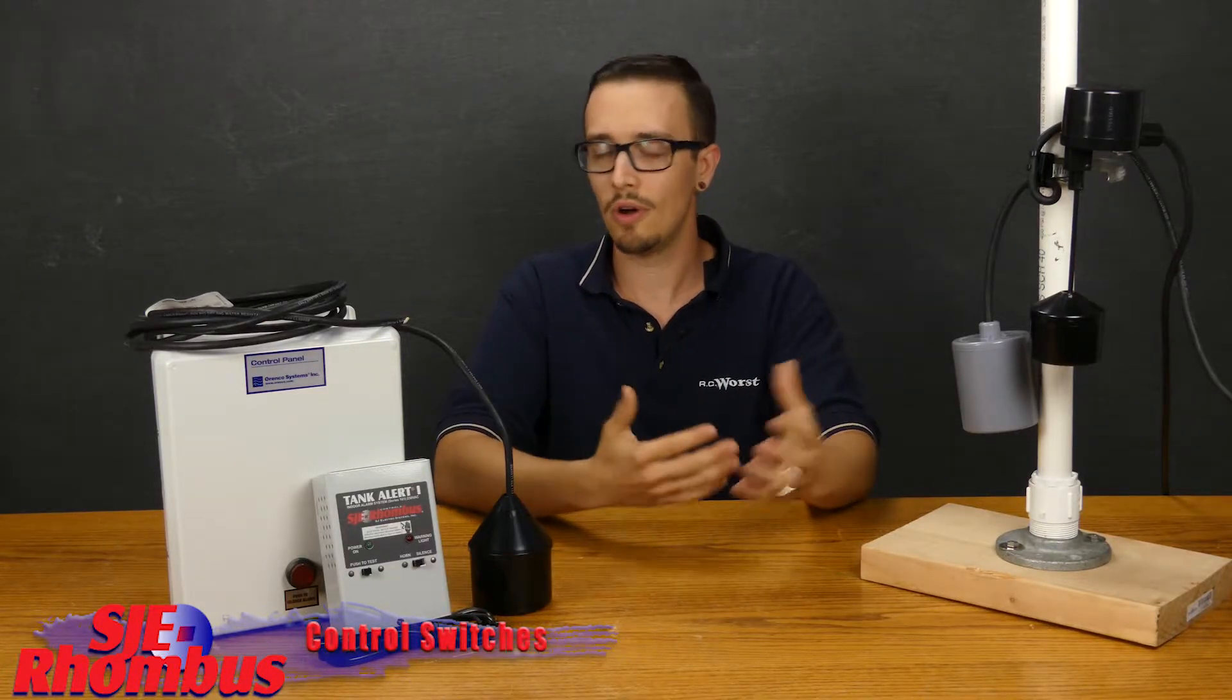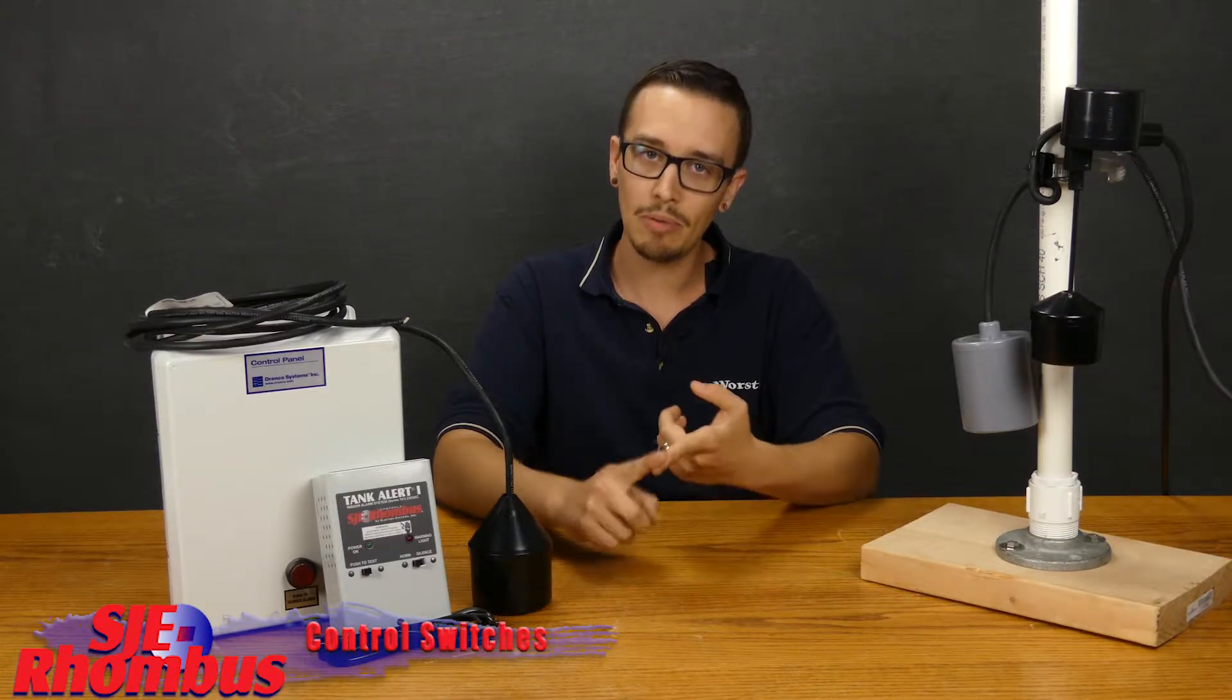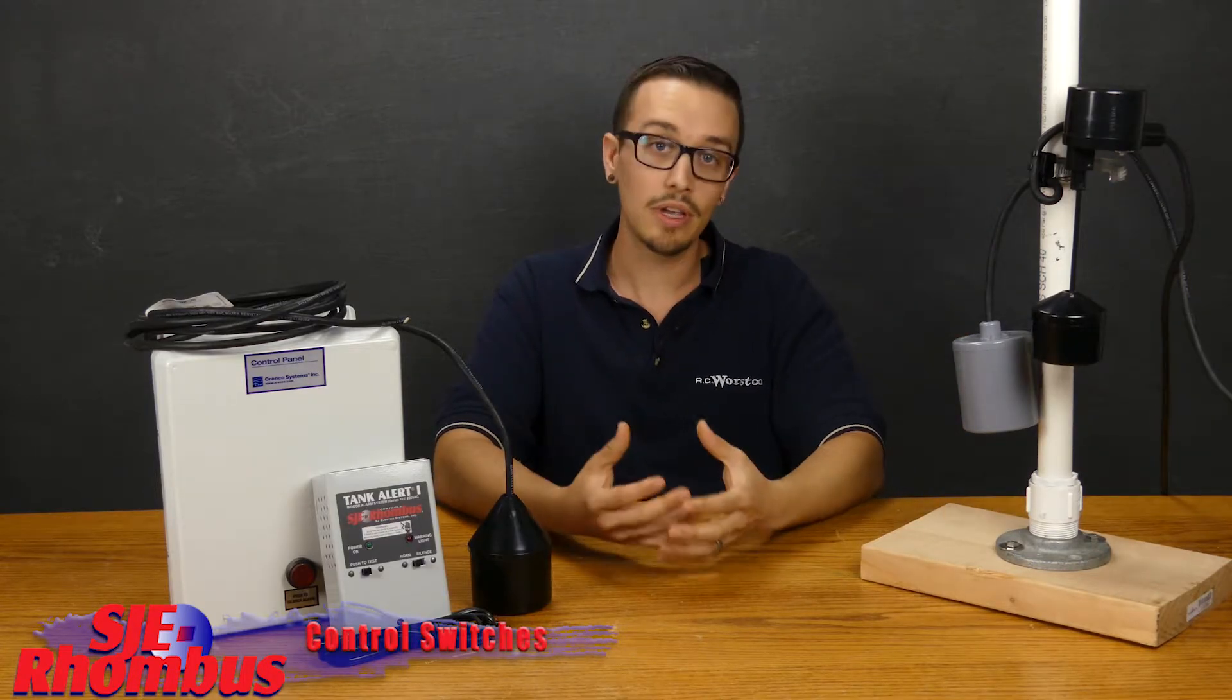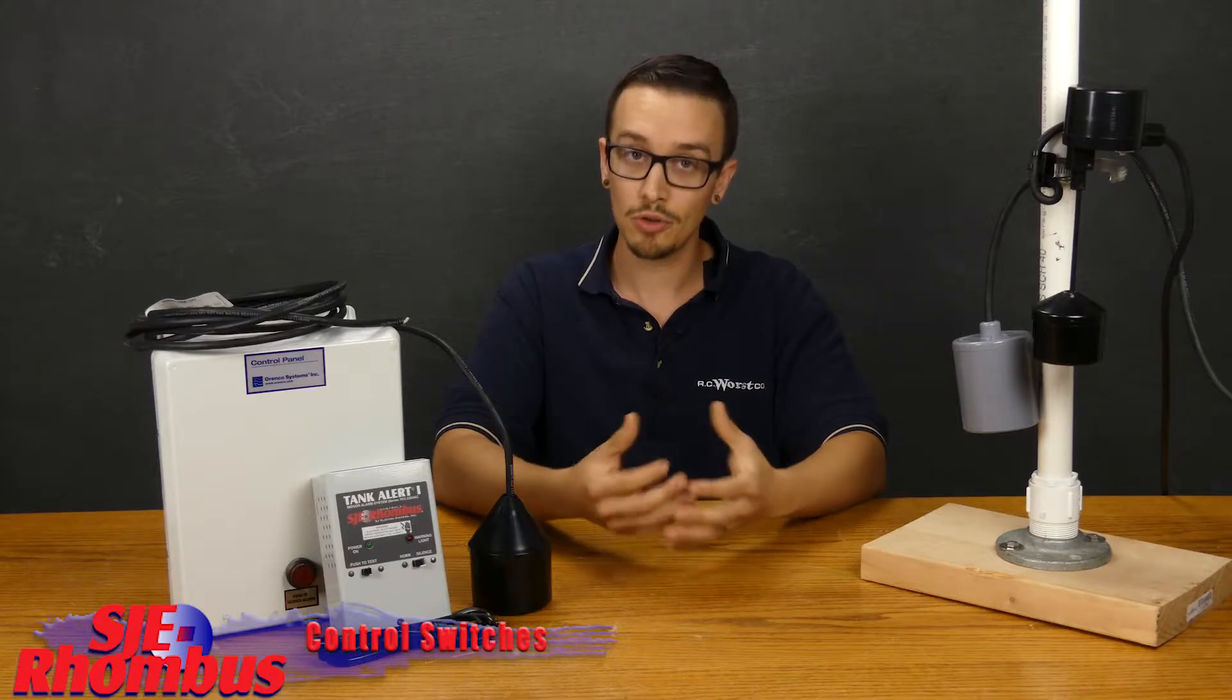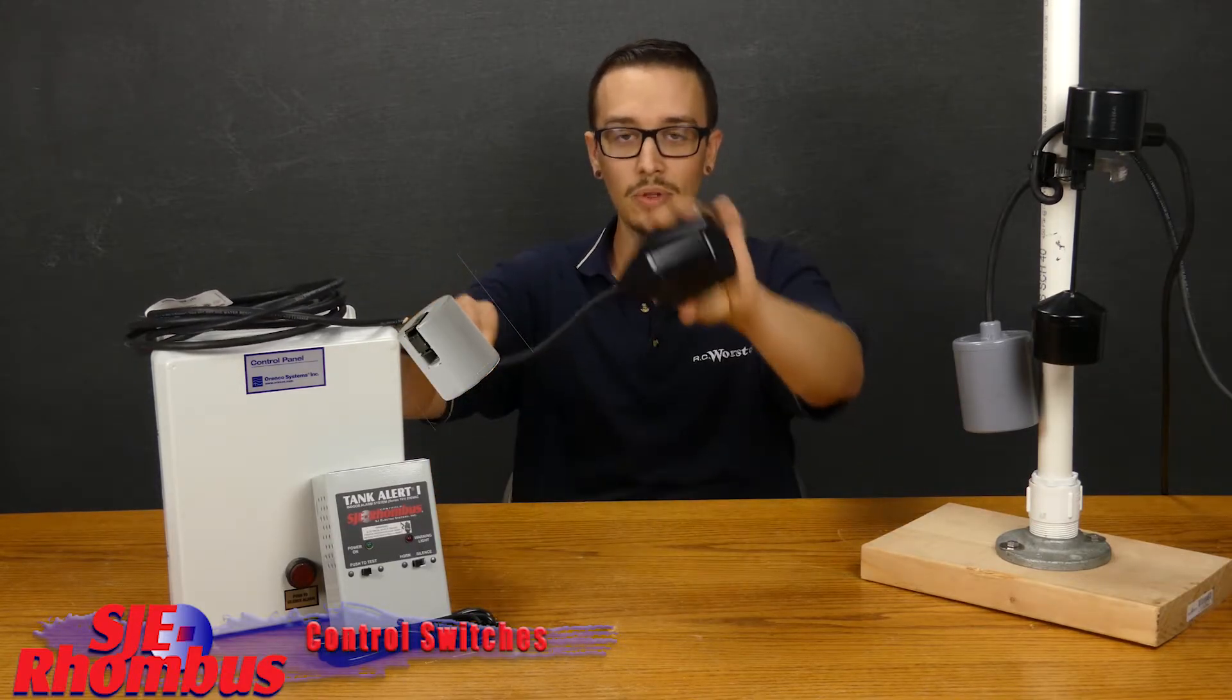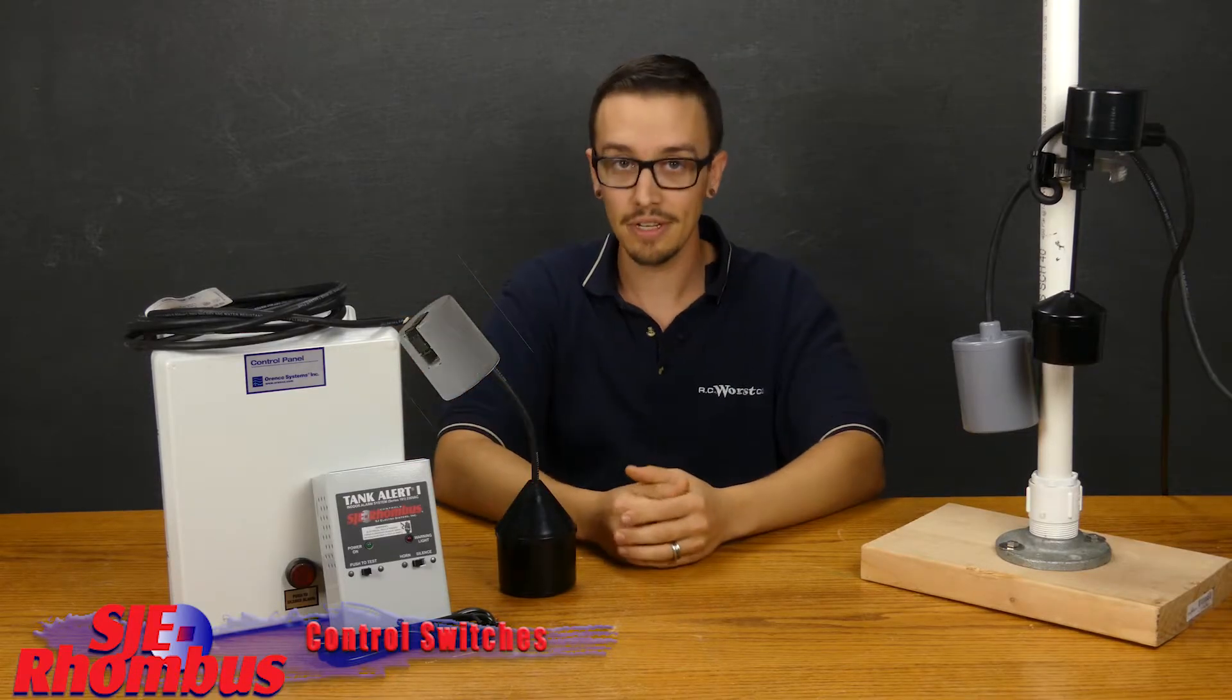These switches are all offered in various mounting configurations, so you can get them with a pipe clamp, which is going to be something similar to what we've got over here where you're able to attach the float switches to the pipe itself, or you can get them with no mounting option, or you can get them with an external weight which is just a small weight that creates a pivot point as the switch hangs down in the tank, and then the float switch will pivot from wherever that weight is attached inside the tank.